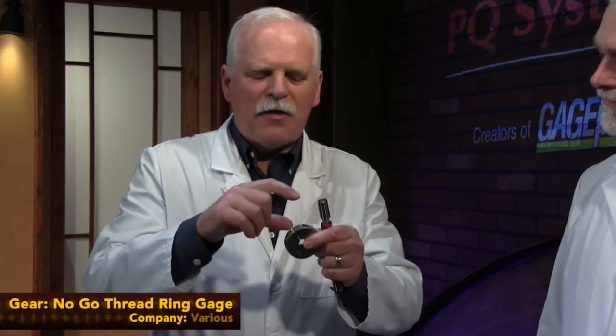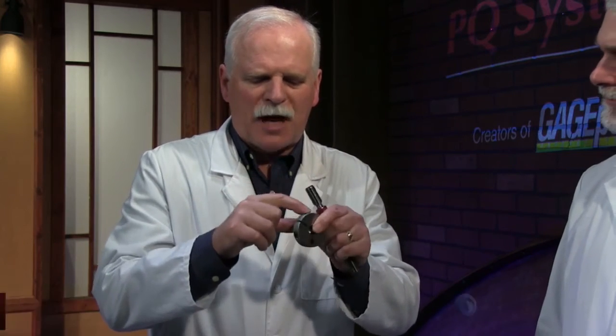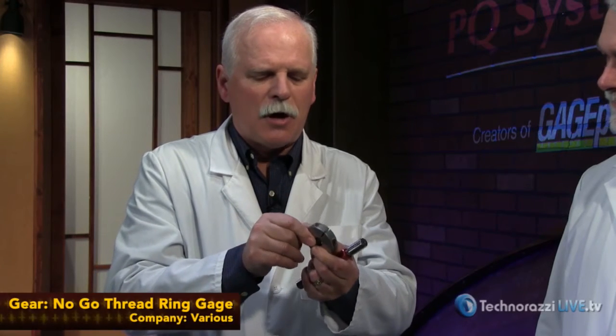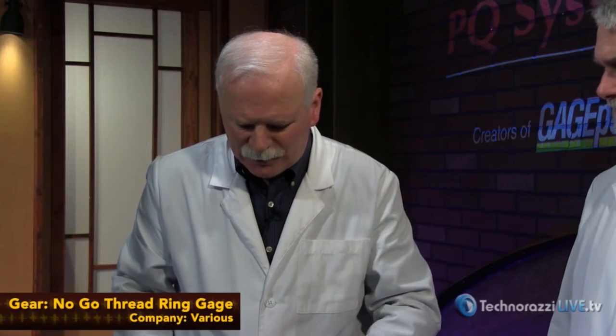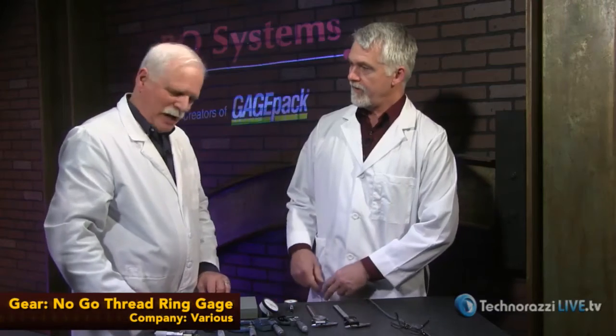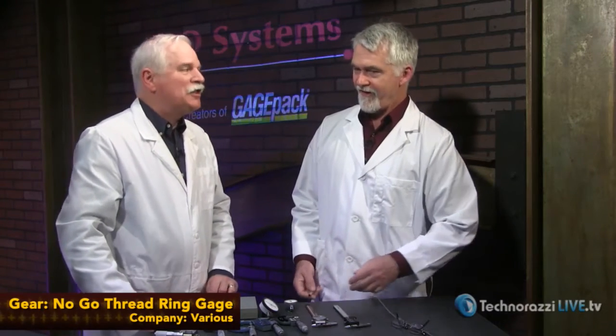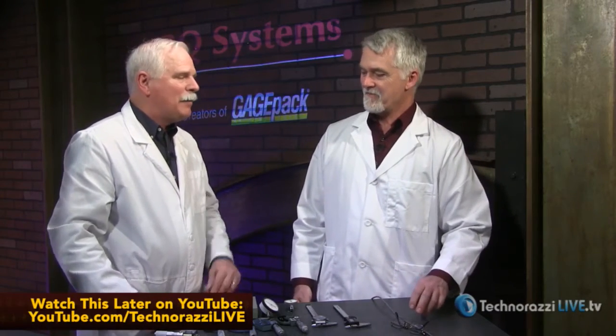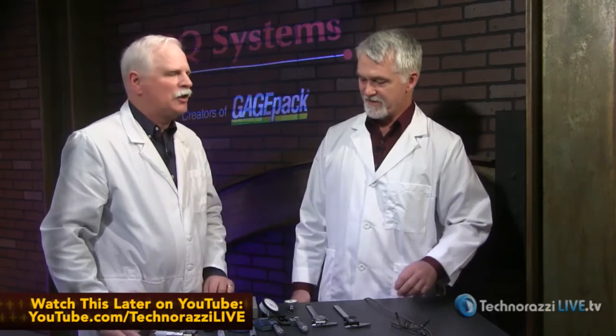Then you'll seal the ends so they're tamper-proof, so the auditor or your customer knows these have not been adjusted in between when they shouldn't have been. So that covers how to calibrate a threaded ring gauge and why we suggest that it's left to a calibration lab. But if you have to do it, that's what you should consider.